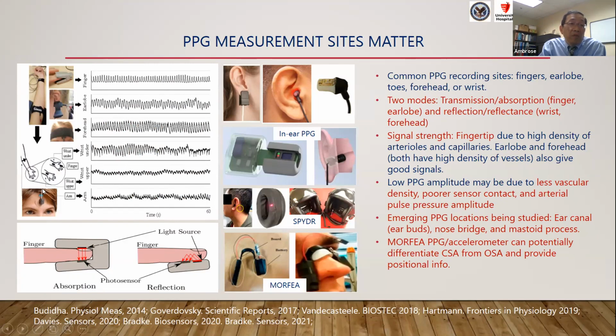You can measure it through the forehead. There are two ways of measuring PPG. One is using the absorption or transmission technique. The other is using the reflection or reflectance technique. For transmission, you have the light source at one end and the photosensor at the other end. For reflectance, they're at the same end. By the way, there are others, such as an ear canal one, and there are ones that measure from the mastoid. They put it in a cup inside a helmet, and for a jet pilot, you can monitor their PPG and heart rate variability and so on.